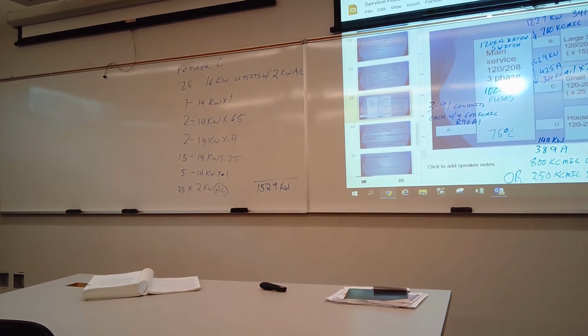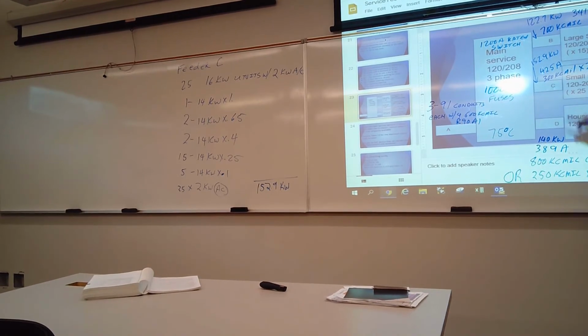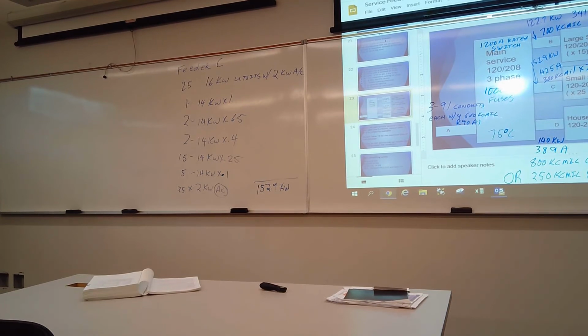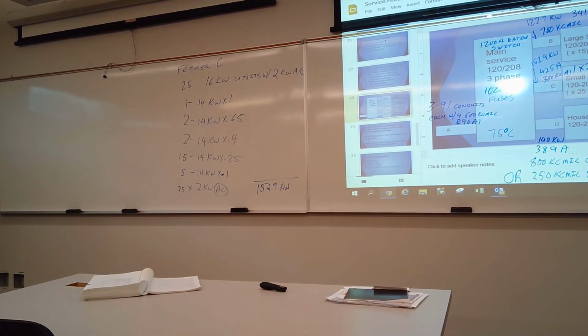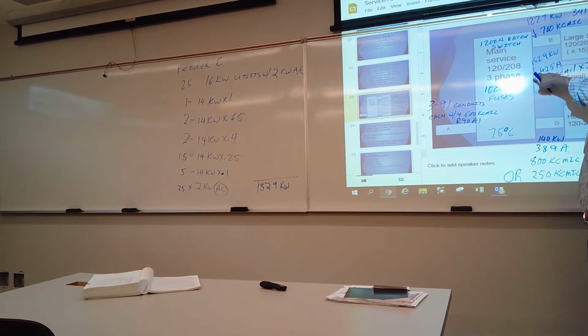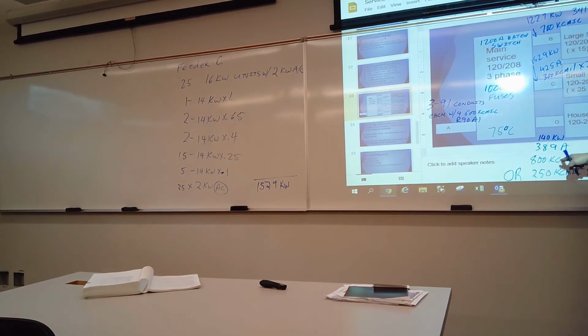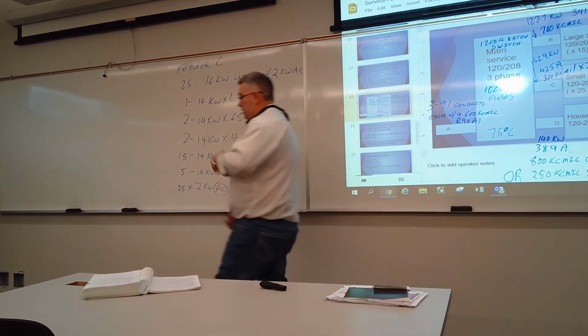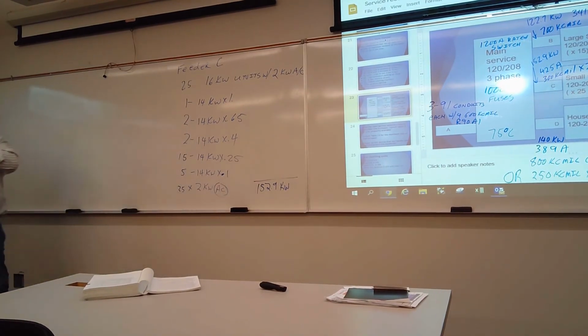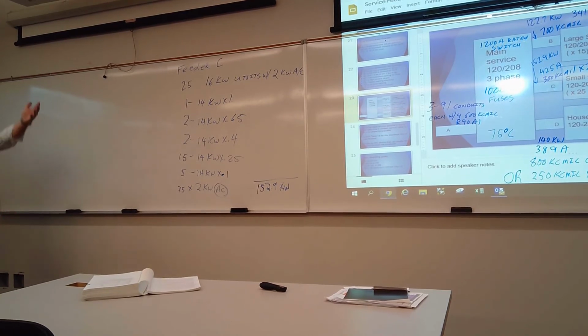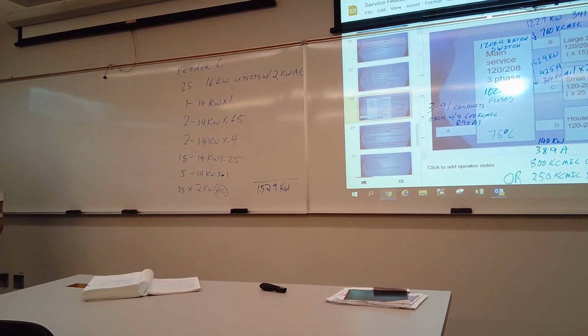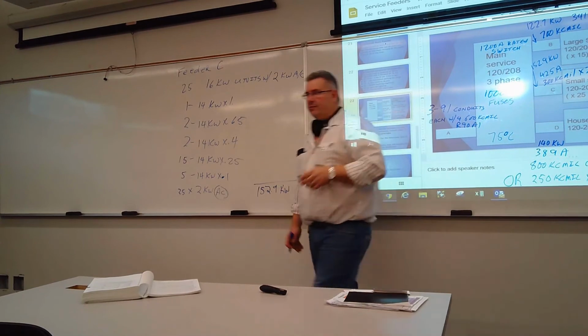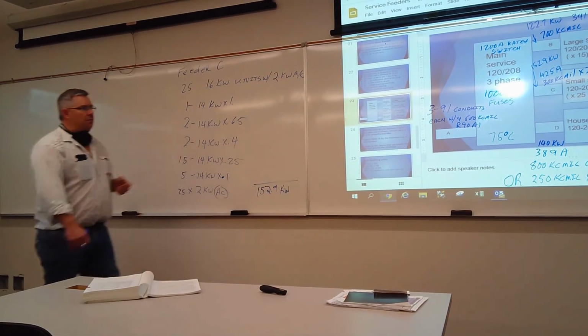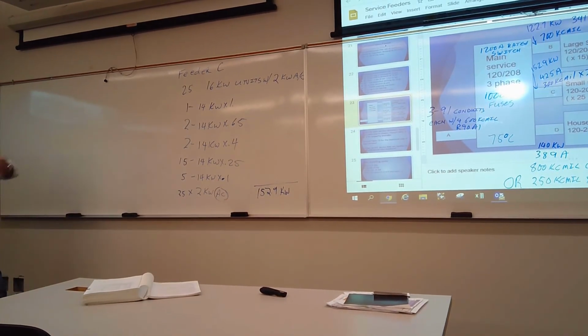As you were saying earlier, when you add up the ampacity of all these conductors, we've got 341 plus 425 plus 390, which is 1150 amps here on these conductors, but you only have 940 coming in, right? And that's perfectly fine. It works out because not everybody's going to be home all the time. If all the people on the top floor happen to be home, you have to allow for it to distribute out, but the chances of everybody using everything at the same time is diminishing. So we can allow for that.